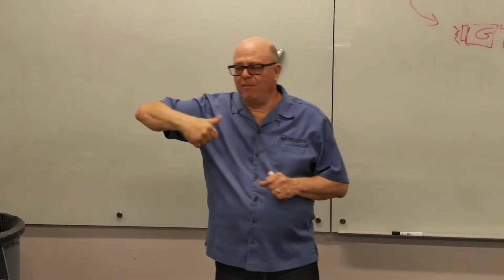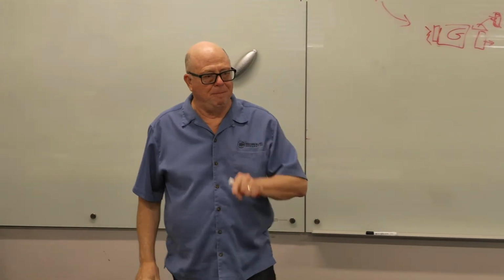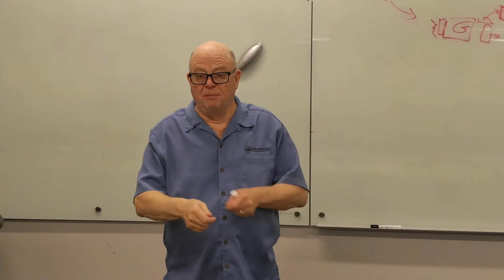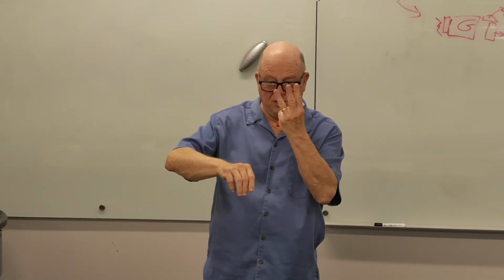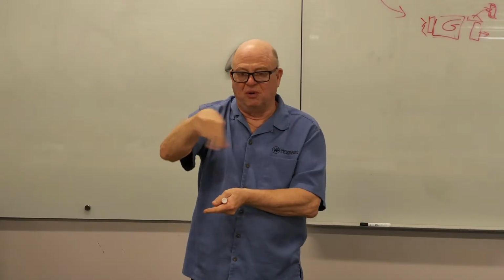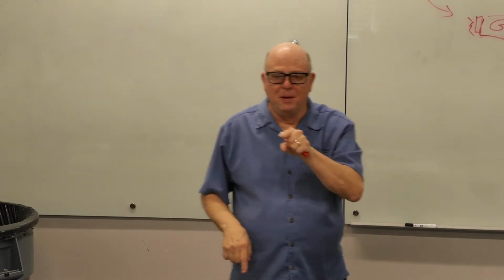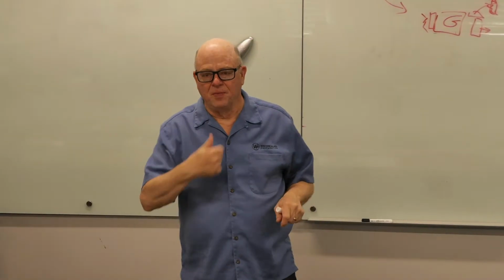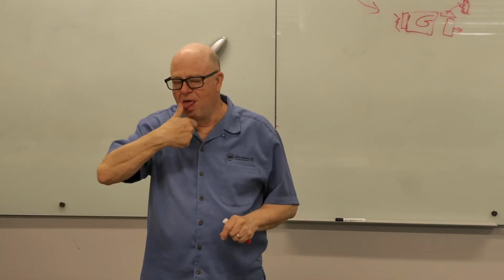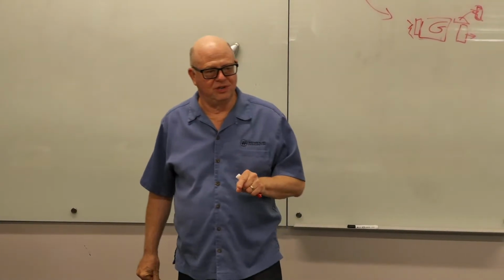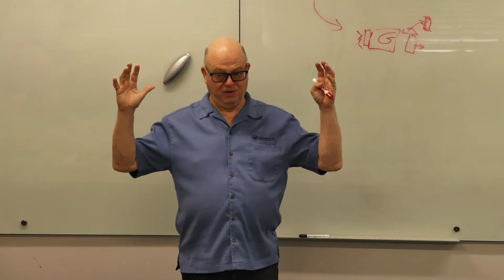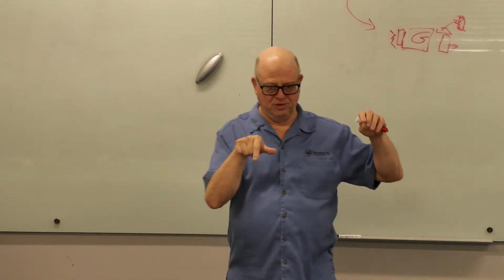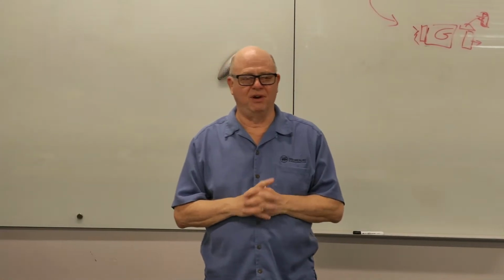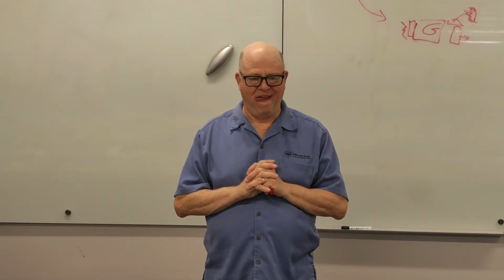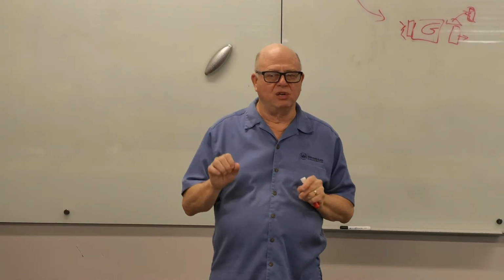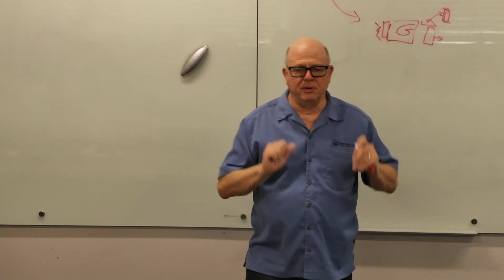So if you take a forward curve fan and you spin it backwards, either because somebody messed up on the motor connections, because three-phase power, if you flop any two, you'll just reverse the rotation. Okay? Forward curve fan, rough order of magnitude. If it's spinning backwards, what percentage of the airflow is it going to move? It's going to move air, but not as much as it would if it was spinning the right direction. Anybody have a guess? A third? Better than that. It's more like 2/3. You're going to be 65 or 70% in that ballpark.